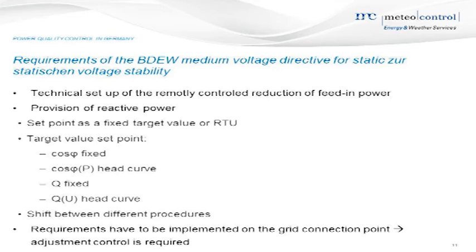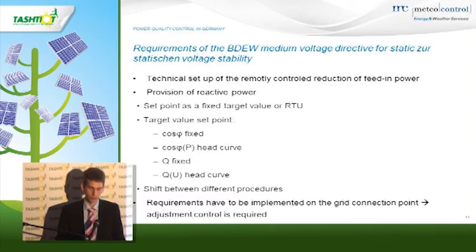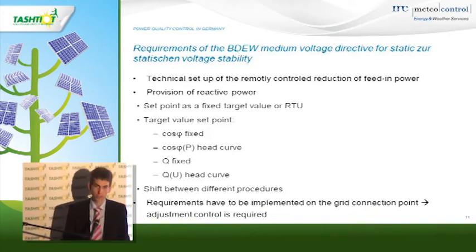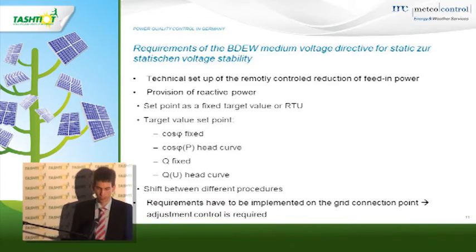So here are just some examples from the requirements out of the medium voltage directive. Of course, you have to control the active power. For the provision of the reactive power, there are different types of how you can do this. You can get a set point by the utility as a fixed value, or curves like cosine phi dependent on the active power, also dependent on the voltage, a fixed reactive power value, or a Q dependent on U, so the voltage curve. Those are the most common curves which are used.